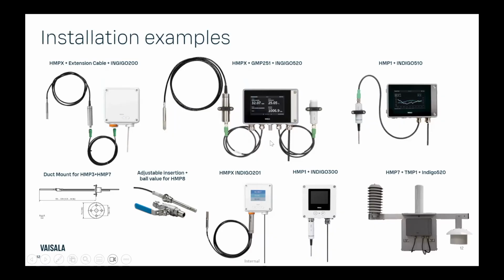In the middle, you have the Indigo 520 supporting two probes. That's actually our CO2 probe, the GMP 251, but we won't touch on that much, but it does do dual probe support. And then on the bottom of that transmitter, you actually see this piece right here. That's a filter that covers the barometric pressure barb fitting. So the Indigo 520 can also be outfitted with a barometric pressure module if you were to say need that in like a lab space or maybe even outdoors. On the right here, we have the Indigo 510 with the HMP1 wall mount with this wall mount bracket. And then on the bottom, we have this weather station. I'm going to touch on this later in the presentation, so I will not get too far into that now.